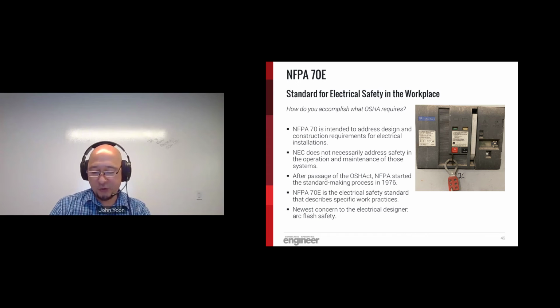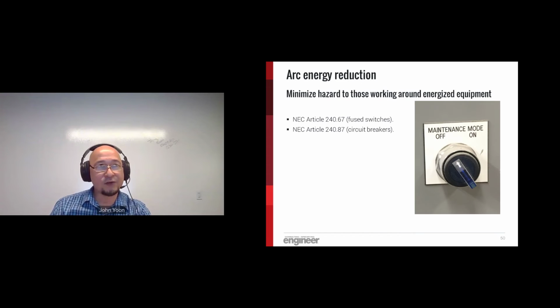So if an electrician needs to work on that piece of equipment while it's still energized, how do you mitigate the hazards associated with that? And more importantly, how many hazards do you have? Typically, the first thing that comes to mind when you discuss hazards is arc flash. The question is, what can you incorporate into your design to reduce that hazard?